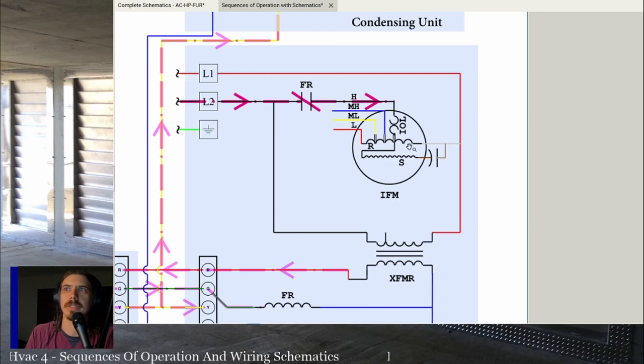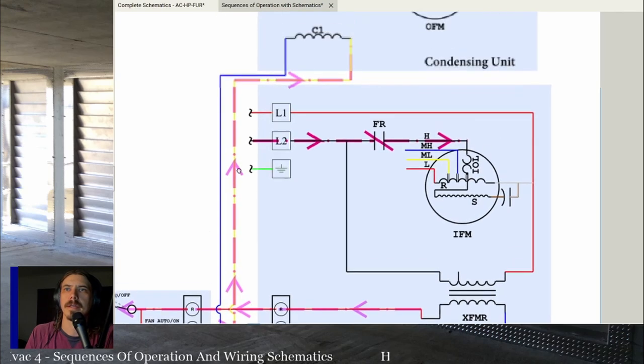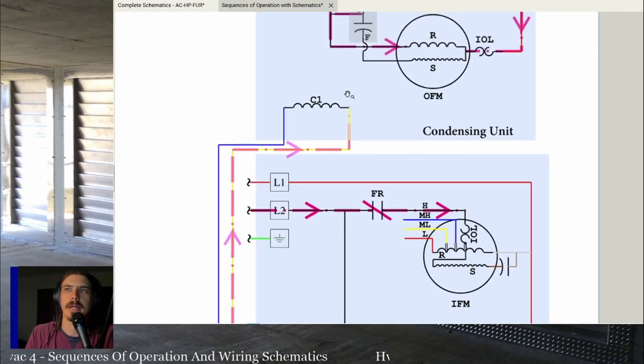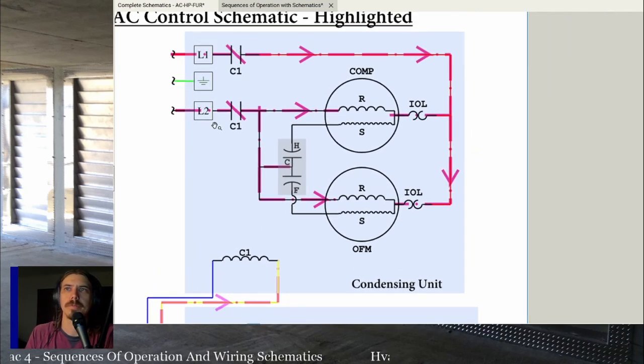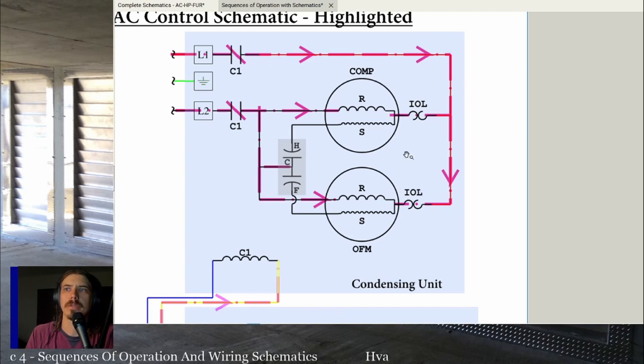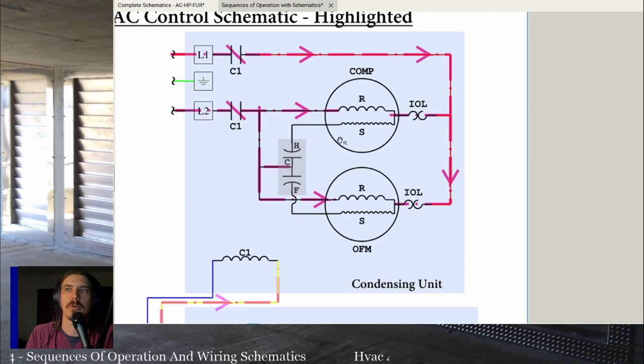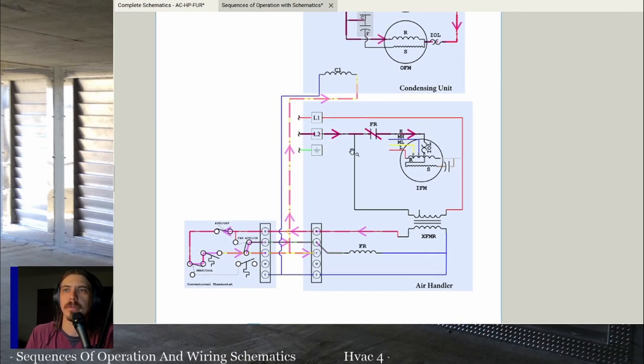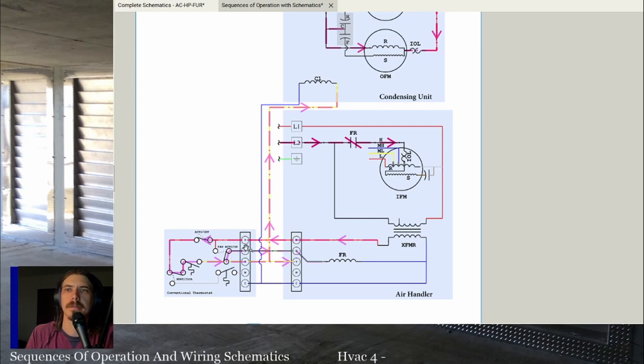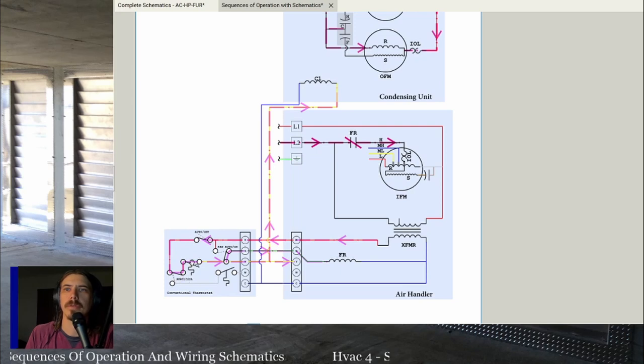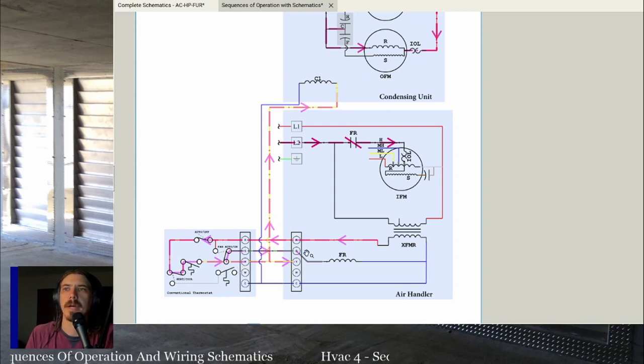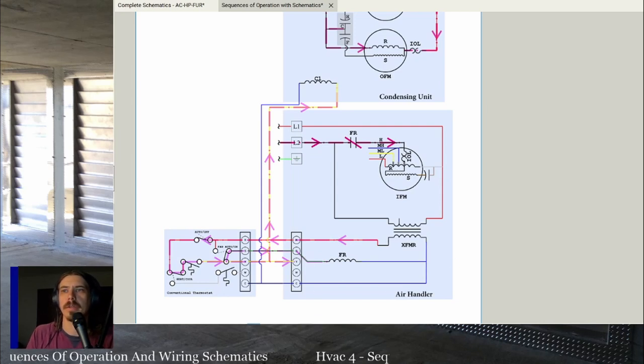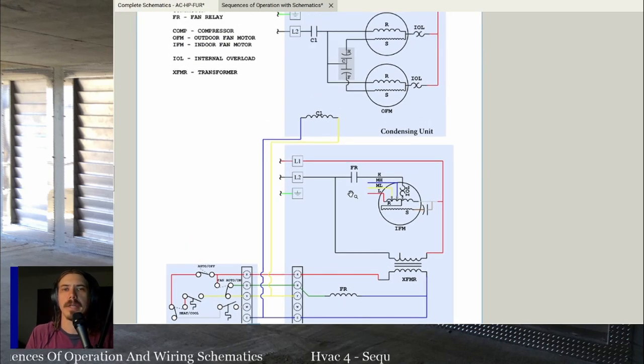Off the Y terminal, power goes up to the outdoor unit and powers the C1 contactor coil. That coil closes both sets of contacts, so power flows through L1 to one side of the outdoor fan motor and compressor, and through L2 to the other side — both motors run assuming everything is operational. That's all there is to an AC-only circuit: 24 volts is sent to the thermostat, power goes through the thermostat to the cooling switch, powers G and Y, Y powers the outdoor condensing unit so it runs, G powers the fan relay so the indoor fan runs. When the set point is reached, all of these shut off and we return to normal state.